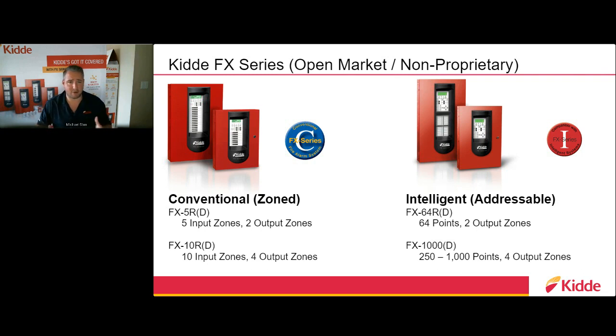To give a basic breakdown, we have conventional panels and devices, and we also have addressable or intelligent panels and devices. On the conventional side, we have a 5-zone system that provides coverage for something like rural Wisconsin, great for a lot of sprinkler monitoring applications. We also have a 10-zone model for larger properties. With our 5-zone you get 2 output circuits, and with our 10-zone you get 4.